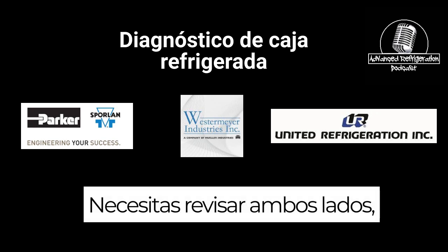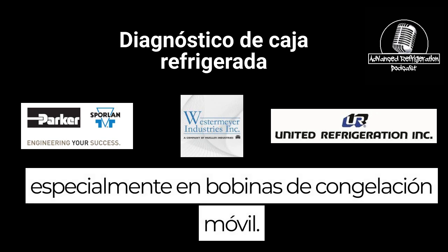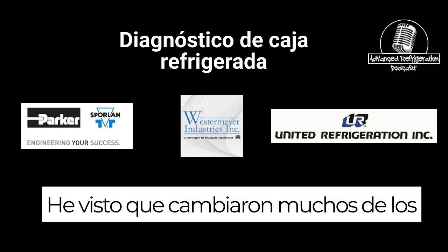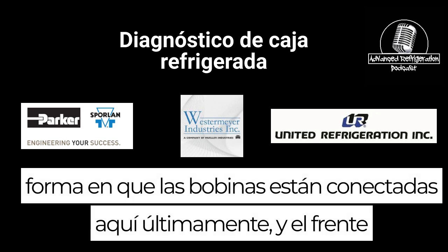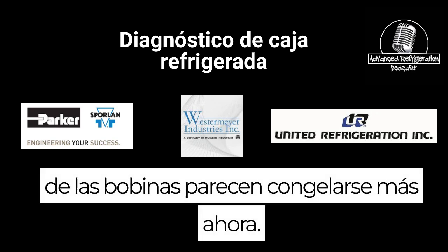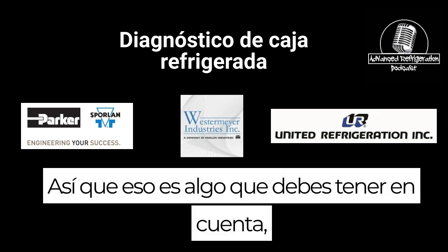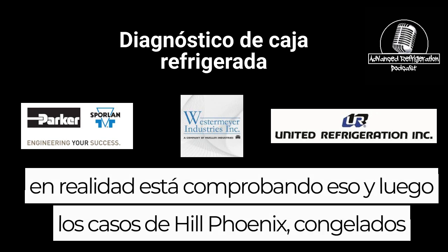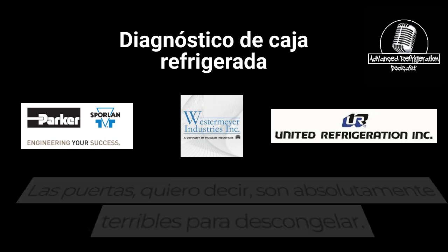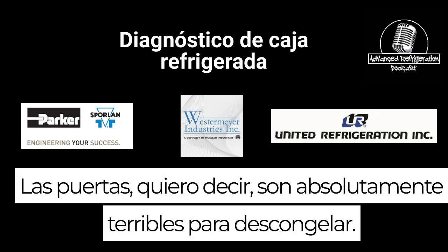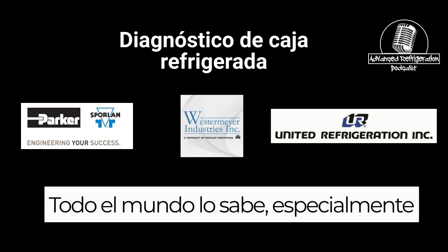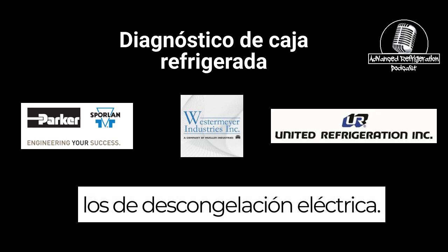So that's one thing to be mindful of. You need to check both sides, especially on walk-in freezer coils. I've seen that they changed up a lot of the way that the coils are circuited lately, and the front of the coils seem to ice up more now. So that's one thing you need to be mindful of, actually checking that. And then Hill Phoenix cases, frozen doors are absolutely terrible to de-ice. Everybody knows that, especially the electric defrost ones.